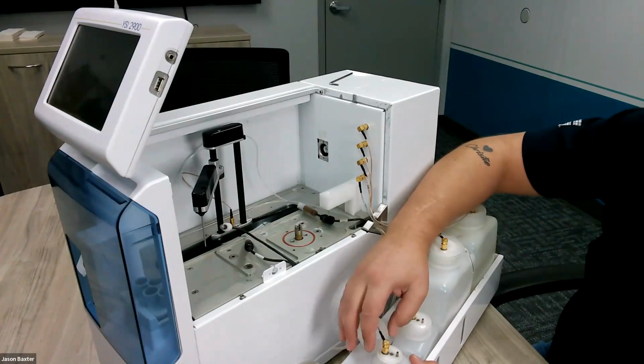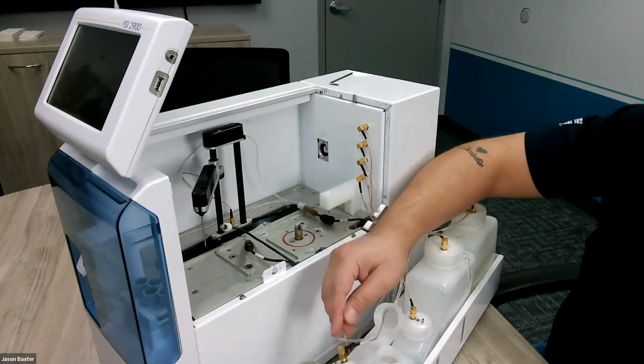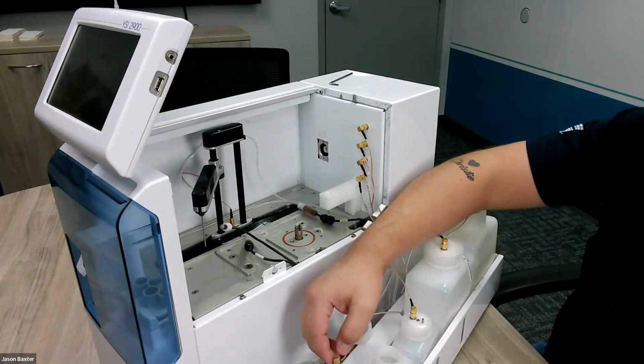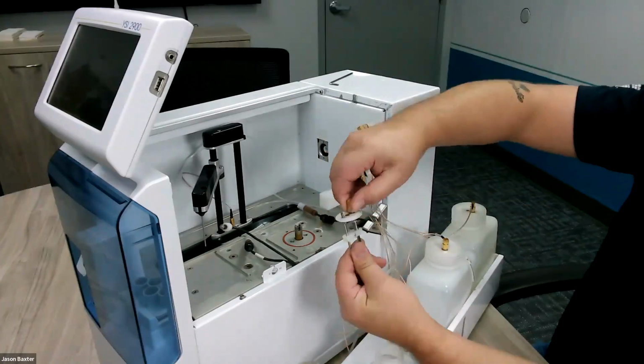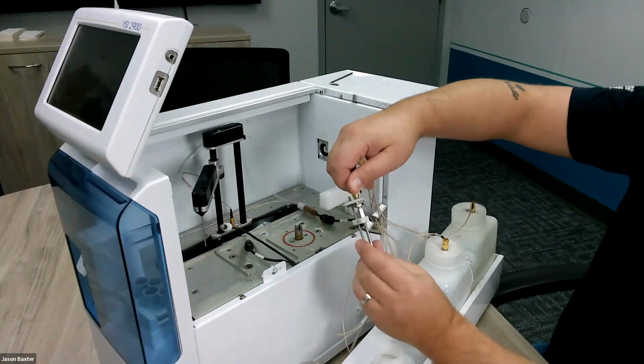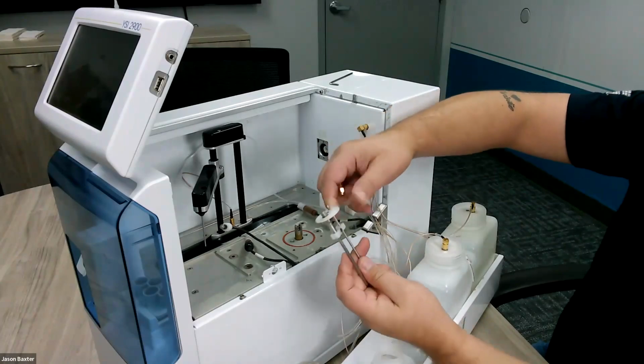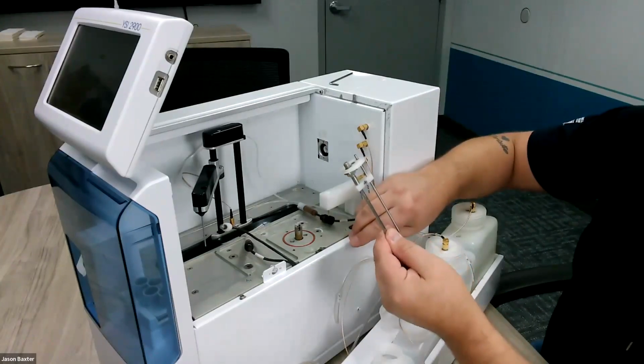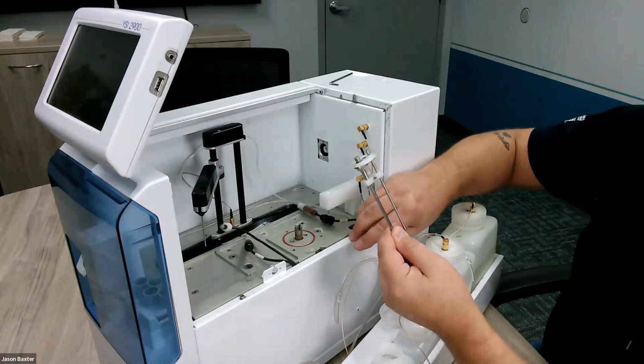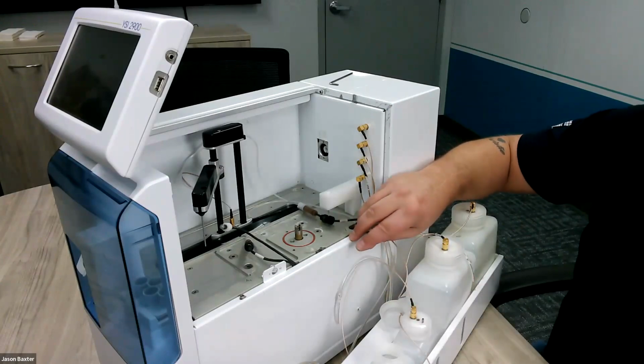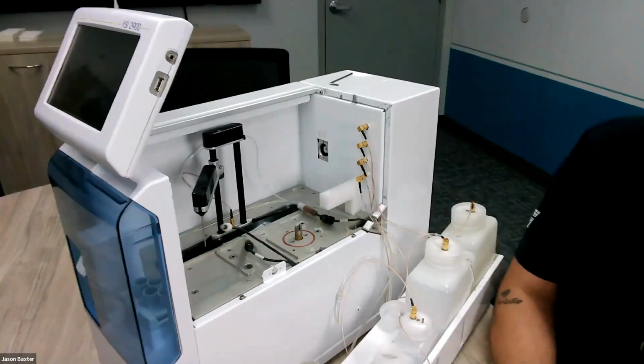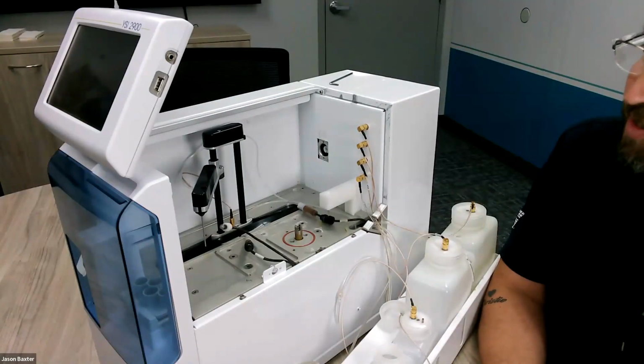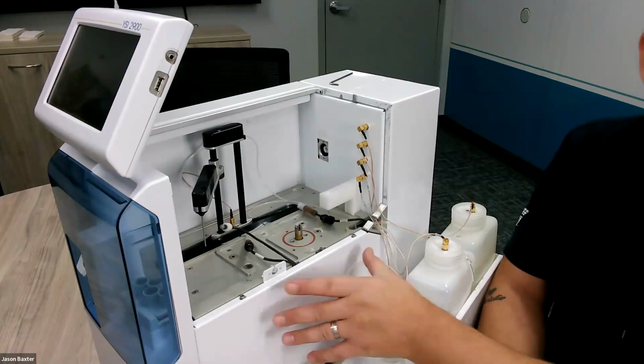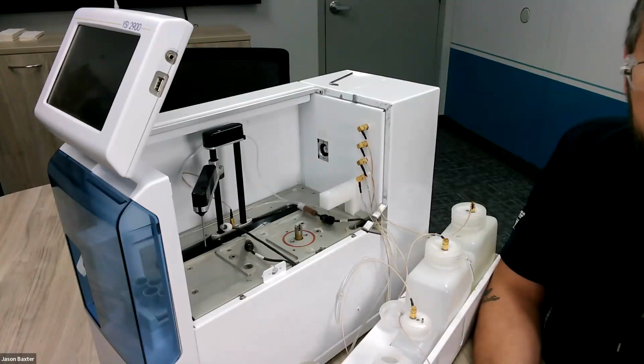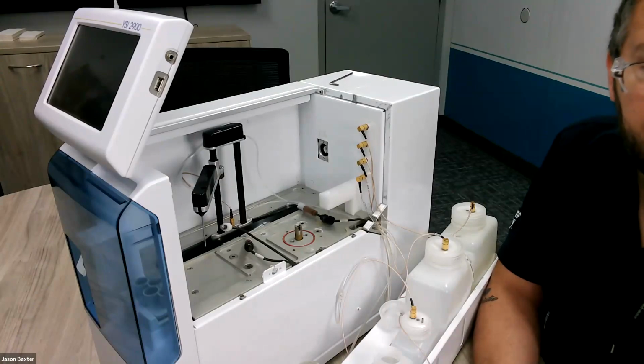Unscrew your threaded retaining ring, lift your cap out, and now we have this gold fitting that connects to your cap. So all you need to do is unscrew your cap from that gold fitting, and now you can take your bottle caps, all 4 of them, and put them in the same bleach water solution you're using to soak your sample chamber and your waste chamber and your sipper pump housing. At that point, you can be ready to move on to the next stage. The next stage is going to be replacing all the tubing that's behind this panel. And I'm going to hand it back over to Ben Sutter so he can give you some info.